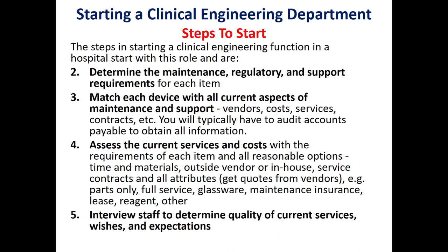The second step is to determine the maintenance, regulatory, and support requirements for each item. We should match each device with all current aspects of maintenance and support — for example, vendors, costs, services, and contracts. We should assess the current services and cost, both in-house and out-house, including materials, spare parts, and everything required.